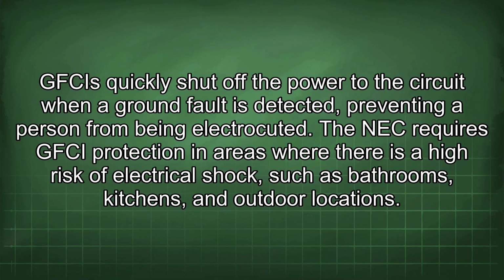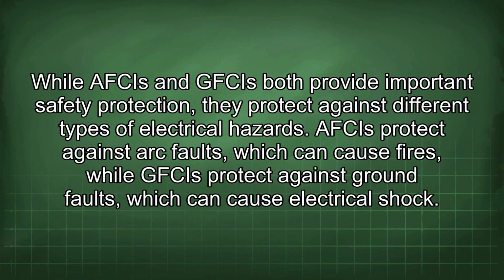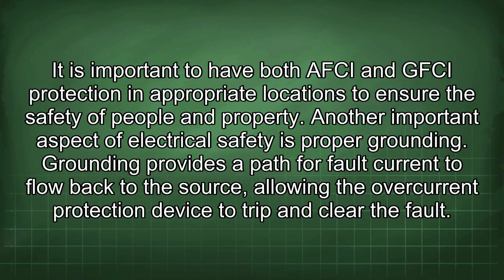kitchens, and outdoor locations. While AFCIs and GFCIs both provide important safety protection, they protect against different types of electrical hazards. AFCIs protect against arc faults, which can cause fires, while GFCIs protect against ground faults, which can cause electrical shock. It is important to have both AFCI and GFCI protection in appropriate locations to ensure the safety of people and property. Another important aspect of electrical safety is proper grounding.